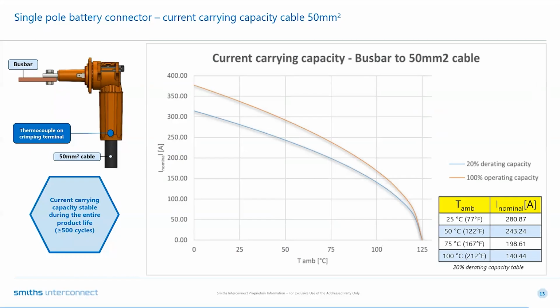The graph shows two different lines. The orange one related to the 100% operating capacity at different ambient temperature, and the blue one related to the 20% derating capacity. The connector, as highlighted in the bottom right table, carries 200 amps, 280 amps at the standard ambient temperature, and close to 200 amps at an ambient temperature of 75 Celsius degrees. One last thing to add, this 300 amps connector size can also be fitted with a 70 square millimeter cable that is similar to a 2/0 AWG size cable, and this will increase the current carrying capacity.